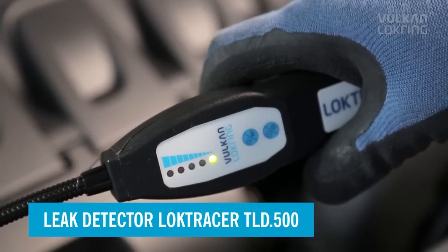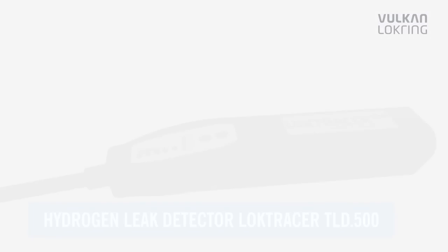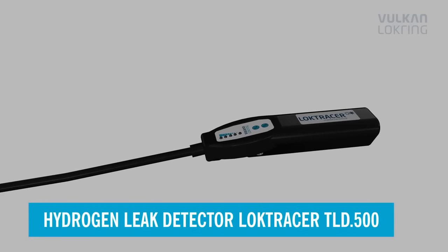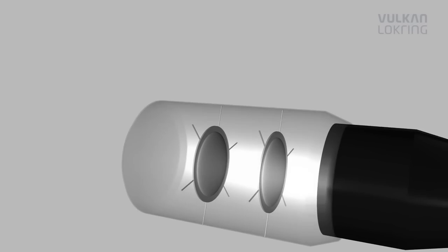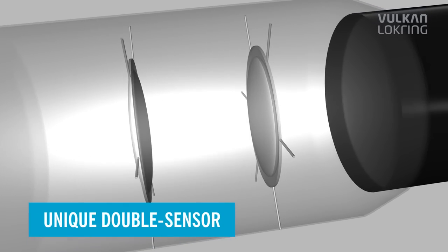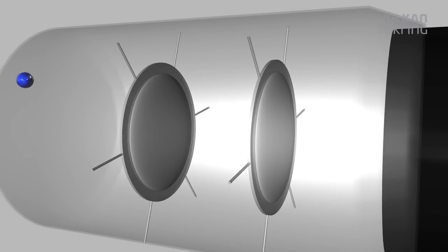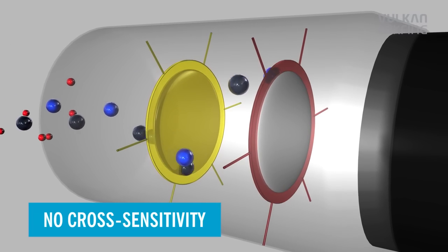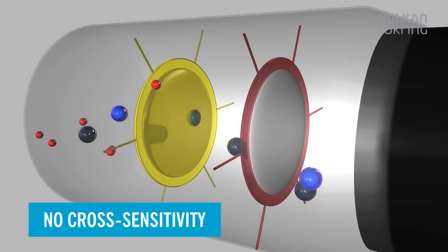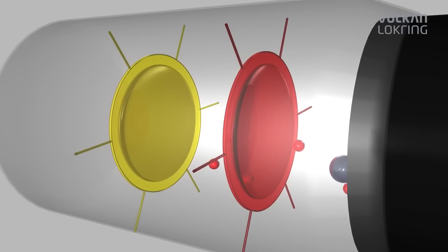The LOKTRACER TLD.500 has a unique double sensor system, made up of a hydrogen sensor and a multi-gas sensor. The multi-gas sensor reacts particularly quickly, and the hydrogen sensor reacts exclusively to hydrogen. Sensor control has been optimized to such an extent that the advantages of both sensors can be optimally used for leak detection.